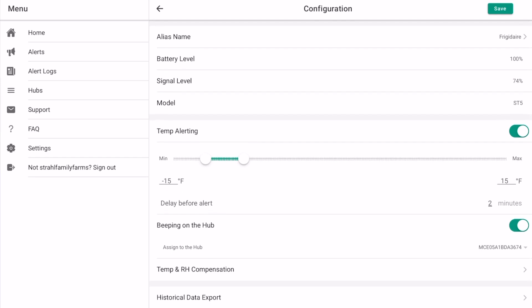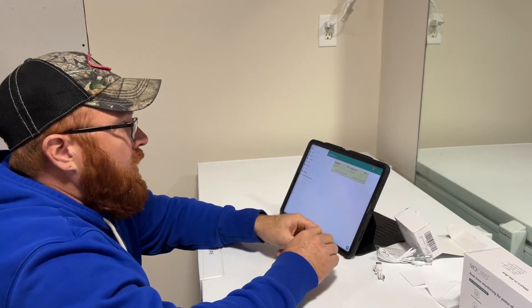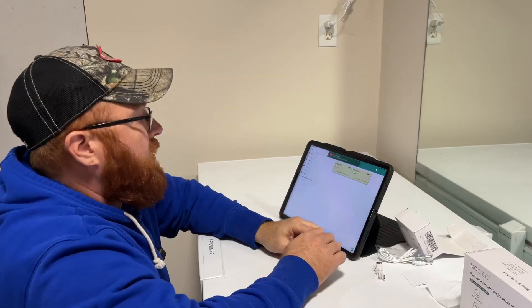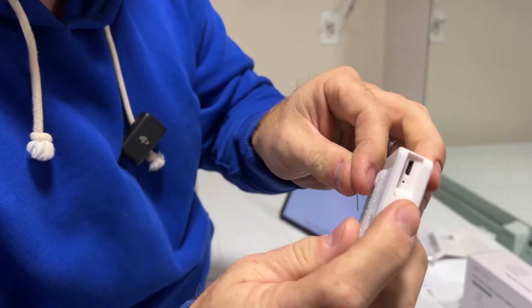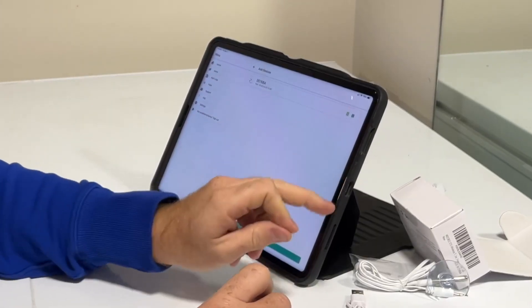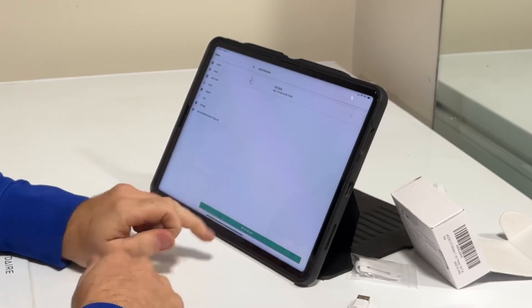You can see what signal level the sensor is running at. The hub is in the same room as the freezers and the signal level is still pretty good. It also shows you the battery level, and you're able to turn the beeping on the hub off if you need to — that hub produces about a 90 decibel sound when it goes off, it's pretty loud. Now let's set up another sensor. I'll hit the plus sign and select ST5 sensor, pair it to this hub. It's asking me to hit that little button inside the door. I poke the button, the screen sees the sensor, I hit the check mark, a blue light starts flashing, then hit Add and plug in the sensor — all set up.